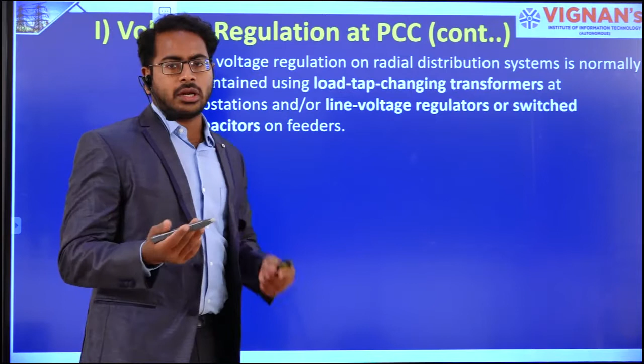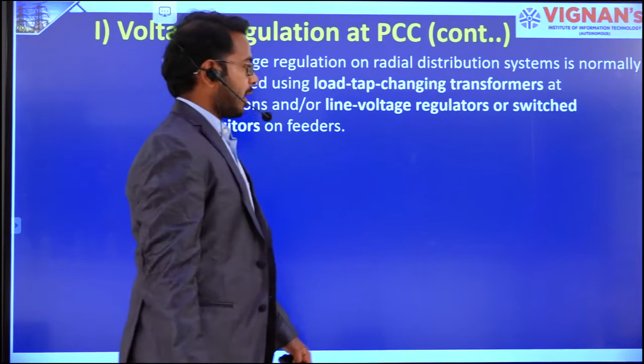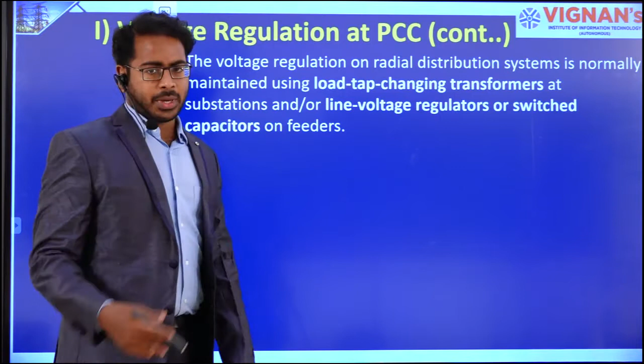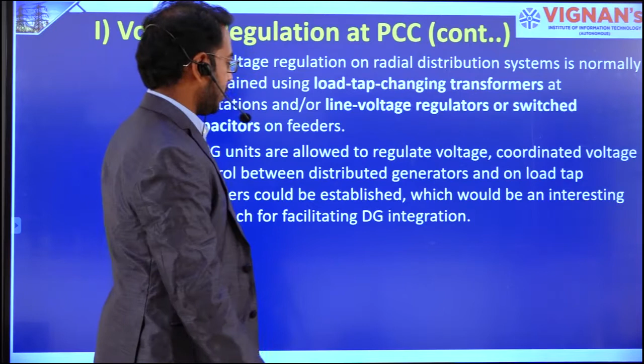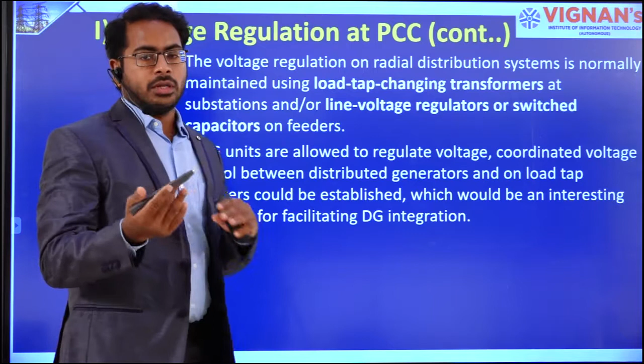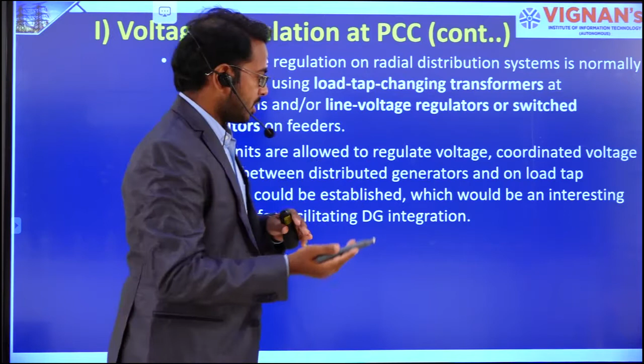So generally, to regulate the voltage on the radial distribution side, we either use load tap changing transformers, or for the feeders we use switching capacitors. If DG units are allowed to regulate the voltage, coordinated voltage control between the DGs and the load tap changers could be established, which would be an interesting approach to facilitate DG integration. If you allow the DG to regulate the voltage, that means we are using a voltage control mode also. For that, we have to coordinate with what is already available in the distribution network, the load tap changing transformer. The DG must be coordinated with the load tap changing transformer, and the DG must coordinate the voltage control.